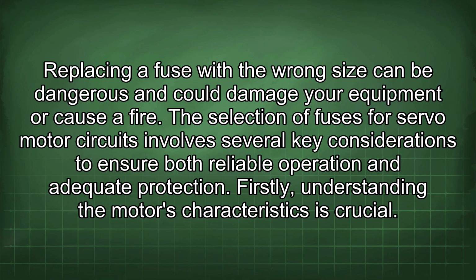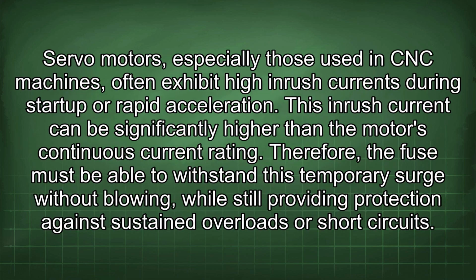The selection of fuses for servo motor circuits involves several key considerations to ensure both reliable operation and adequate protection. Firstly, understanding the motor's characteristics is crucial. Servo motors, especially those used in CNC machines, often exhibit high inrush currents during startup or rapid acceleration. This inrush current can be significantly higher than the motor's continuous current rating. Therefore, the fuse must be able to withstand this temporary surge without blowing, while still providing protection against sustained overloads or short circuits.